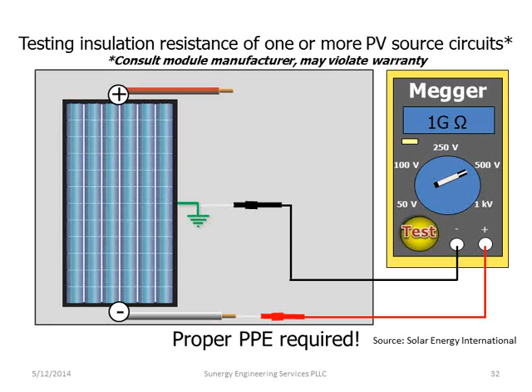So, the best way to do this, in the way that it's done by the module manufacturers, is they short the leads, and they put the positive conductor on the shorted leads, and they put the negative conductor onto the frame, and they test it that way. So that way there's no difference in voltage through the modules. There's no chance of damaging the diodes, and there's only a difference between ground and the two shorted leads. But in order to short a string, where you might have a 600 volt string, you have to have a special arc flash type of switch that can handle that, doing that over and over again. So that was a good point, actually.